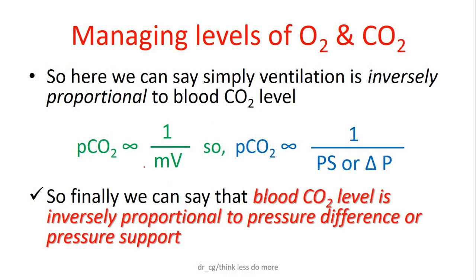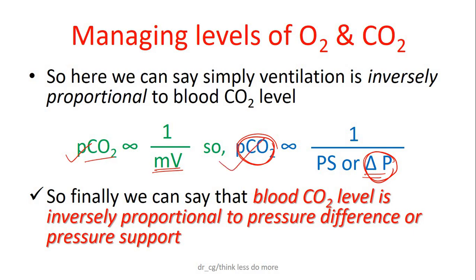We also know that ventilation is directly proportional to the pressure difference. So with these two facts, we can say that the level of CO2 is inversely proportional to the pressure difference. The main important point to remember: level of CO2 is inversely proportional to the pressure difference.